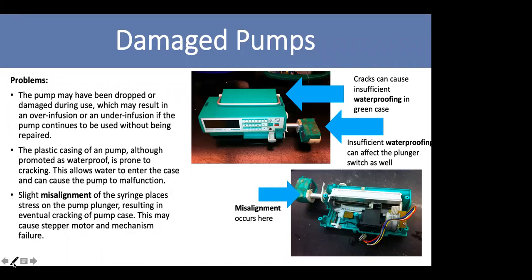And another thing, when you drop it, the mechanism of the syringe pump itself or the volumetric pump can break, get damaged or misaligned. So these are common things that you're going to see in a damaged pump. In the second photo, you can see a misalignment on the syringe pump itself due to a drop. The internal part is broken and misaligned. That can stress the pump plunger and the stepper motor itself and cause unwanted error alarms. That's due to the damage itself.